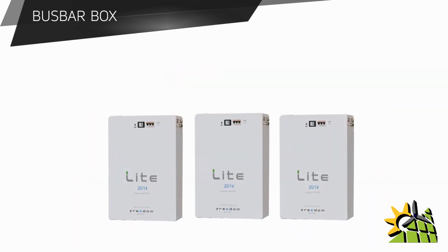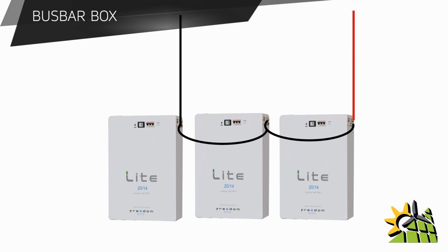On lithium batteries, it is essential to have a battery busbar box. The old way of connecting lithium batteries together is you'll have one negative cable going to the first battery, and then you'll have a loop from that negative pole to the second battery and a loop to the third battery. A positive cable would be connected to the last battery bank's positive pole, and again contractors would loop that cable to the second bank and then to the third battery.